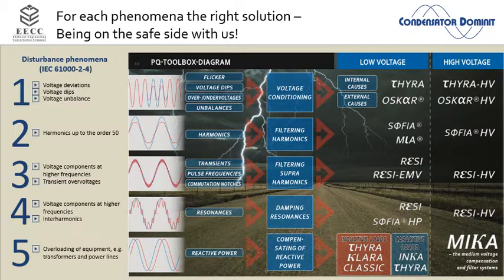Now all these problems can be solved, and I'll speak about that in more detail later. But as a memory point, all RMS voltage fluctuation problems can be solved in two ways. Either I push as much reactive power into the grid as I can, or I put a series transformer in somehow. To simplify it: every problem caused by myself, I can fix with reactive power. Every problem coming down from upstream, I need a transformer to inject voltage and fix it. I'll show you more detail.